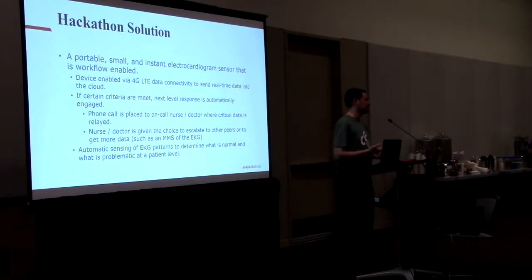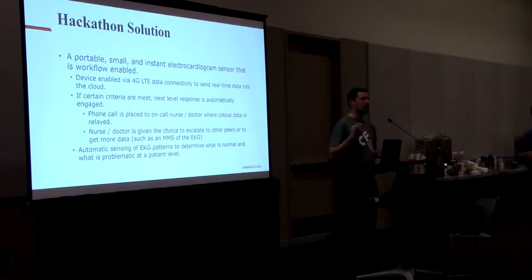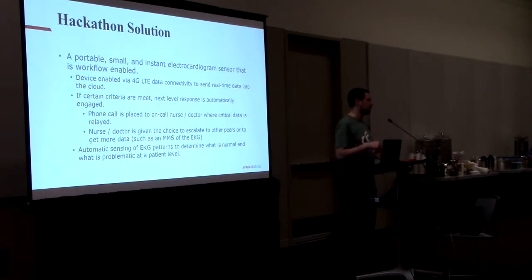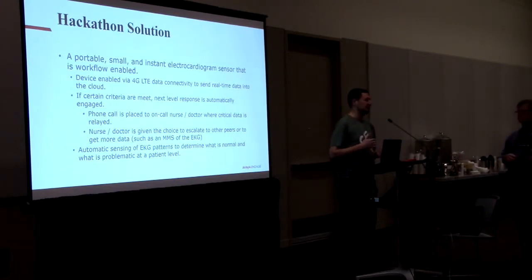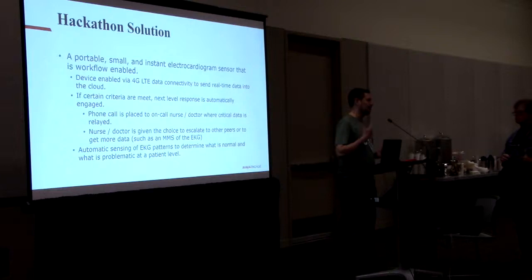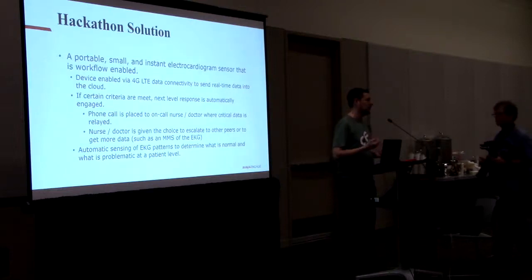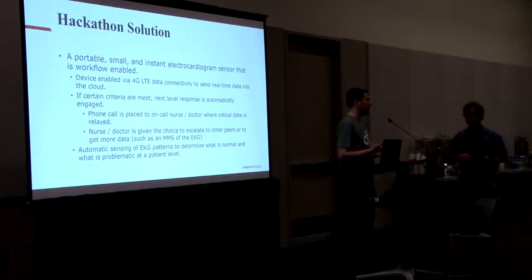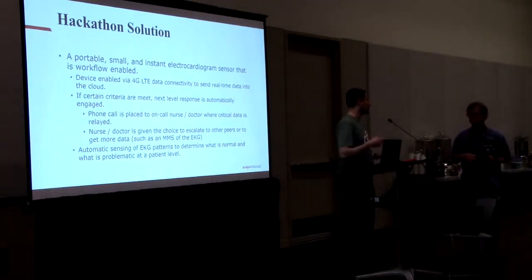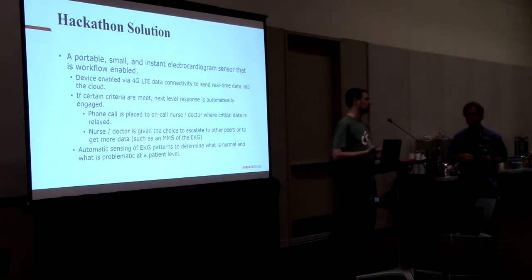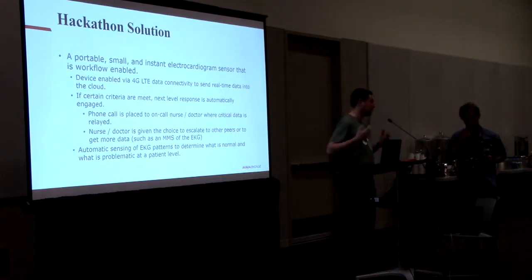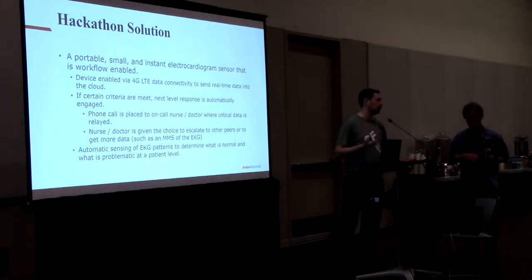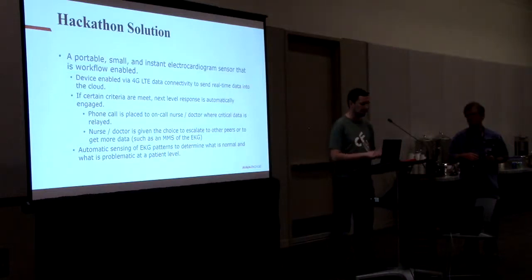They can also escalate, so the system right now also escalates to a conference call over multiple people that can be selected by the unit. For example, the doctor gets the call saying, hey, a person is in alarm. It can automatically go into a conference call that can bring in certain people to start the triage process while they're further away from the patient.